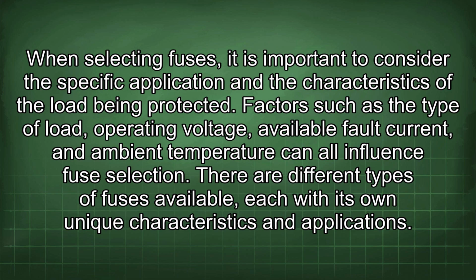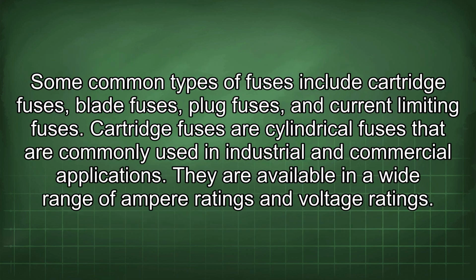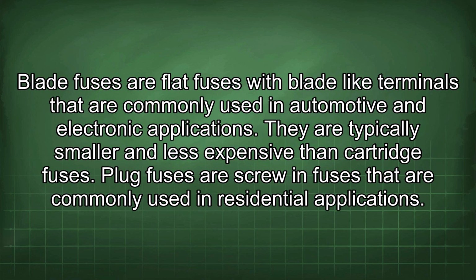There are different types of fuses available, each with its own unique characteristics and applications. Some common types of fuses include cartridge fuses, blade fuses, plug fuses, and current-limiting fuses. Cartridge fuses are cylindrical fuses that are commonly used in industrial and commercial applications. They are available in a wide range of ampere ratings and voltage ratings. Blade fuses are flat fuses with blade-like terminals that are commonly used in automotive and electronic applications. They are typically smaller and less expensive than cartridge fuses.